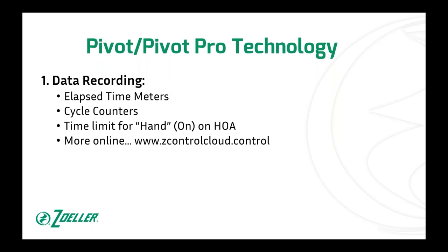We'll go through four technology categories. First, data recording: these panels record elapsed time meters and cycle counters standard — no extra charge. There's a time limit on running pumps using hand on the HOA. There's also a lot more data being recorded online at ZControl.com that will be available to anyone putting panels up online.